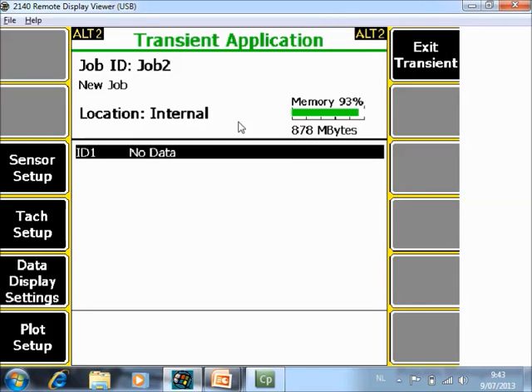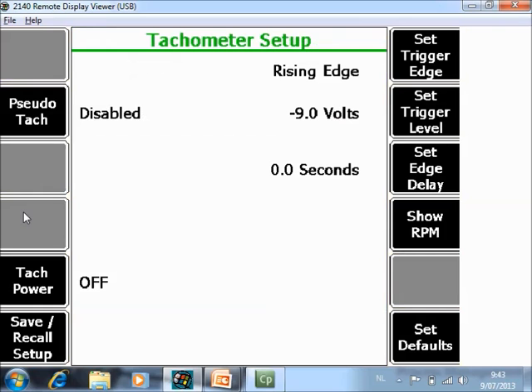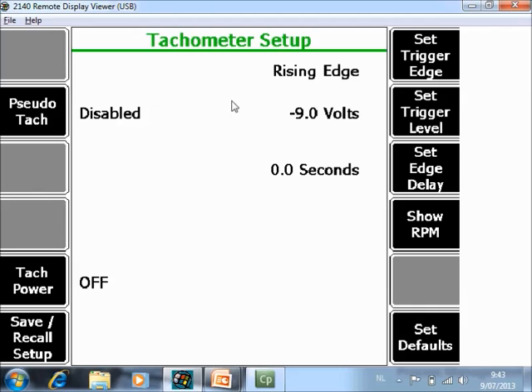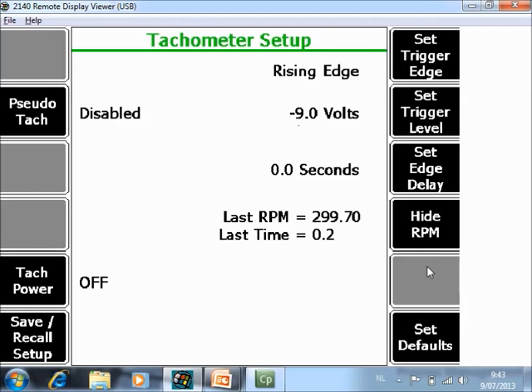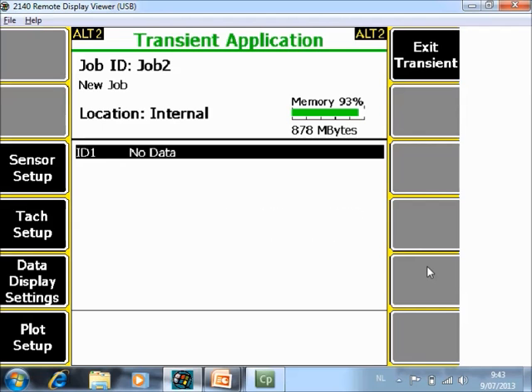You can also check your tach. In this case I am working with a magnetic pickup, so the power is off and the trigger level is negative. There is also a dedicated video tutorial on how to configure tach. I go to show RPM. The tach signal is coming in, so the tach is working fine.